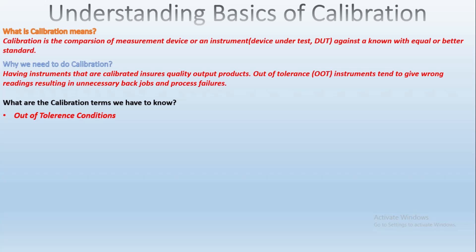The next term is optimization. Adjusting a measuring instrument to make it more accurate is not part of a typical calibration, and is frequently referred to as optimizing or nominalizing an instrument. This is a common misconception — only reputable and experienced calibration providers should be trusted to make adjustments on critical test equipment.